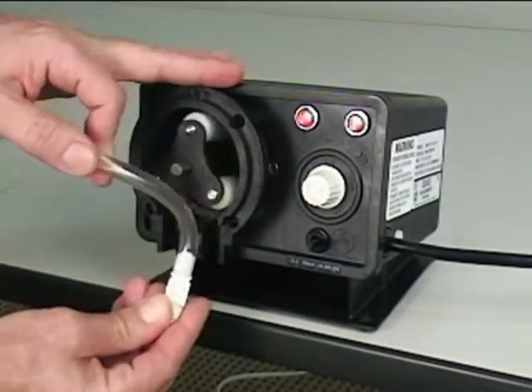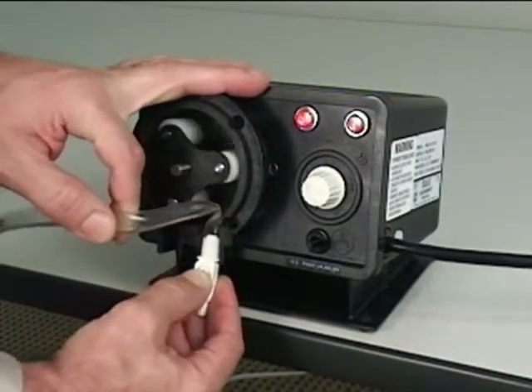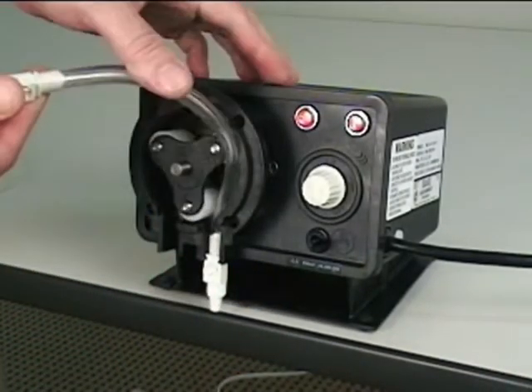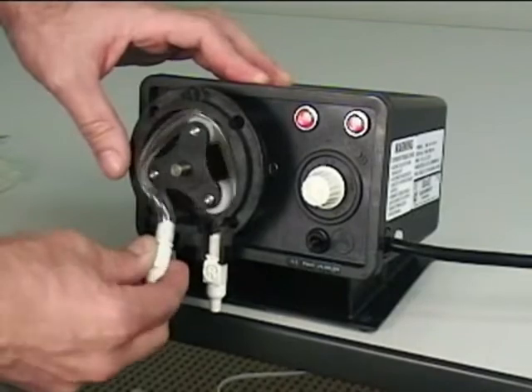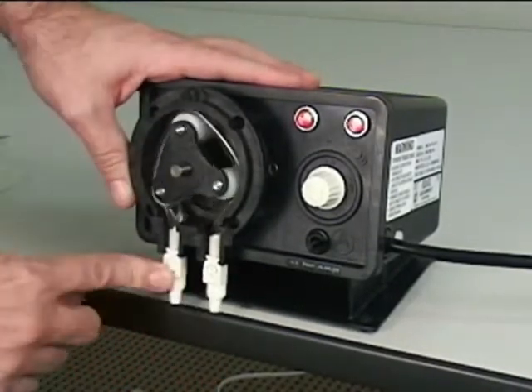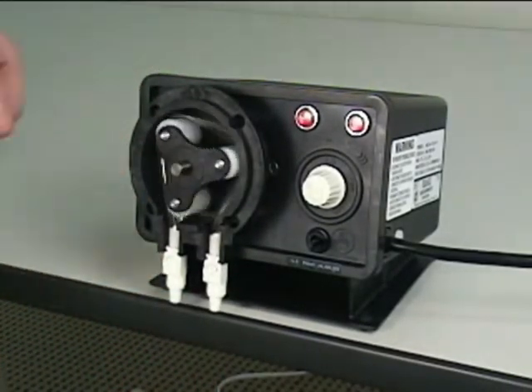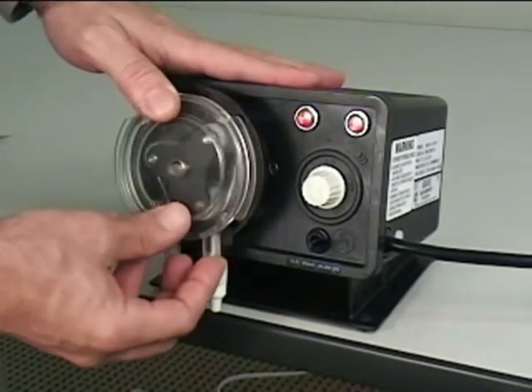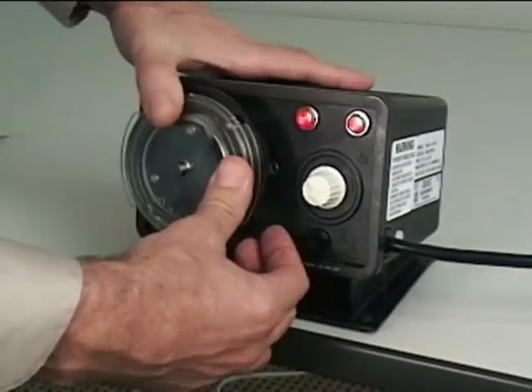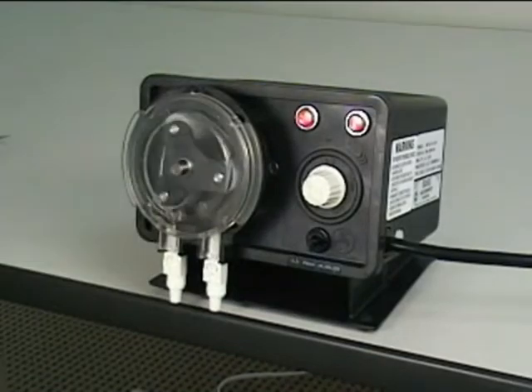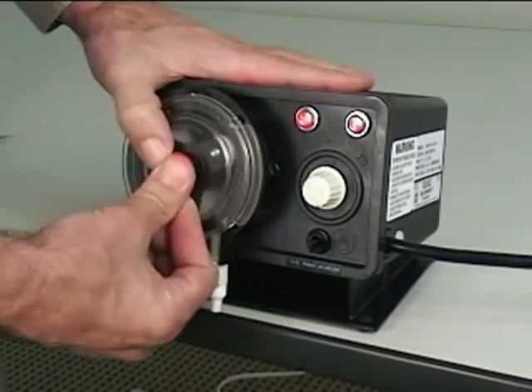Install the clean roller assembly into the pump head. Be sure the words "this side out" are facing the front of the pump. Align the D-shaped hole over the motor shaft and push the entire assembly all the way into the head. To install the new pump tube, the pump must be running. Apply power to the pump and turn the power switch on.